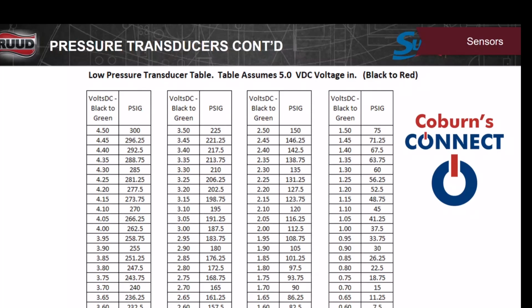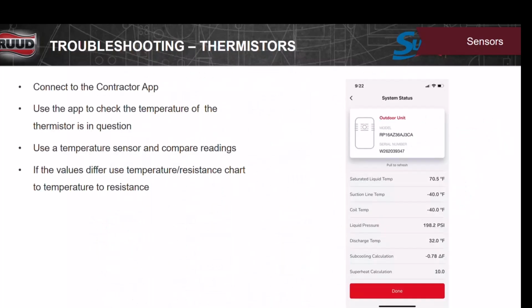Now, this chart can be found on the Coburn Connect app. We have it in there as a calculator. We have one for the liquid transducer and one for the suction transducer. Whenever you connect to the contractor app, you're able to go see the thermistors, the readings of your thermistors. I would go match these up too, and then check them to make sure that that's what it's doing.